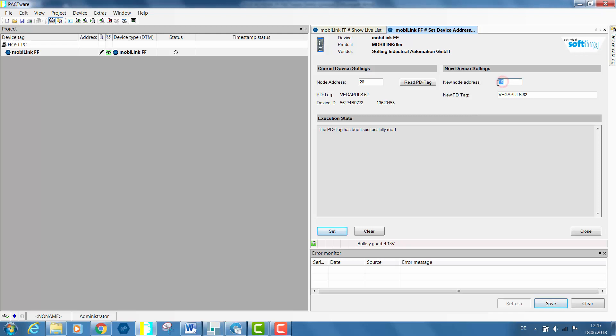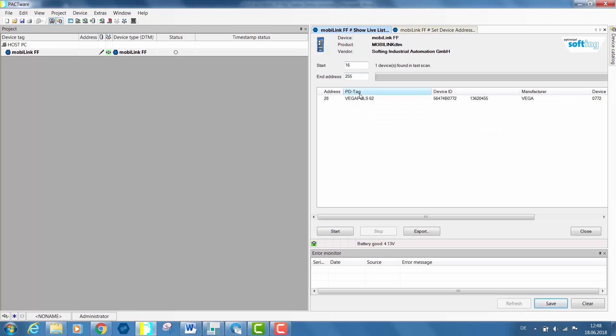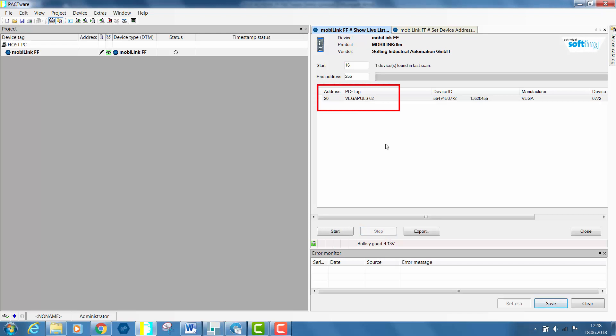Enter 20 in new node address and set the value. The MobiLink is now communicating with the field device to change the node address value. You can verify that your value has been properly configured by refreshing the show live list. You can notice that the Vega sensor has got the address value 20.